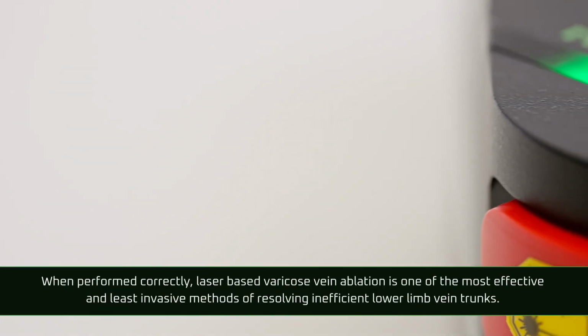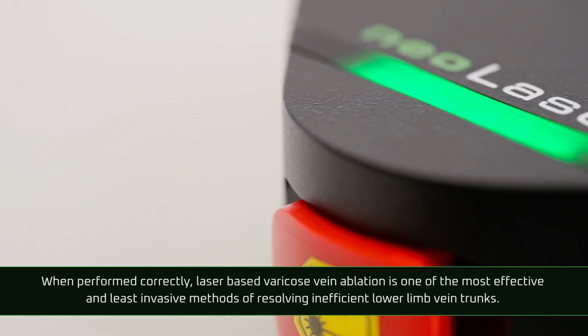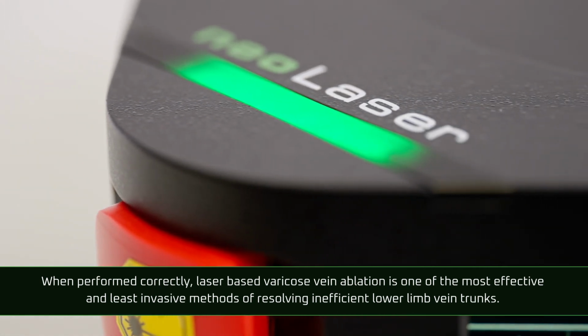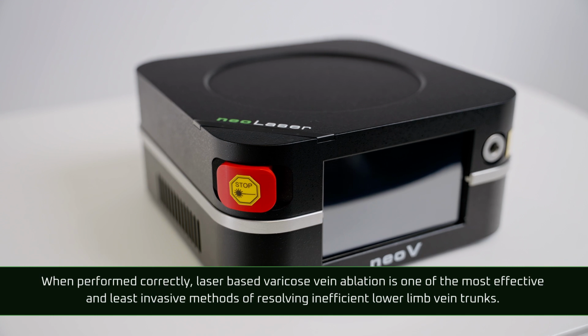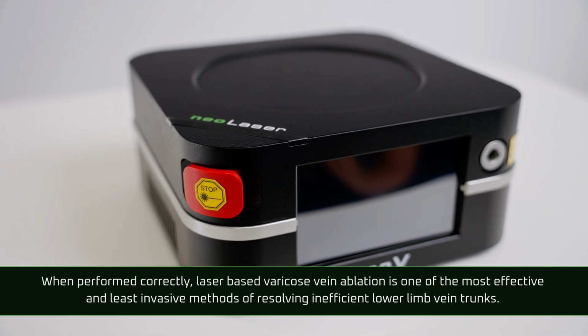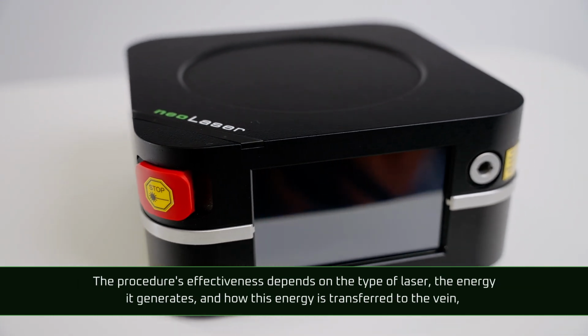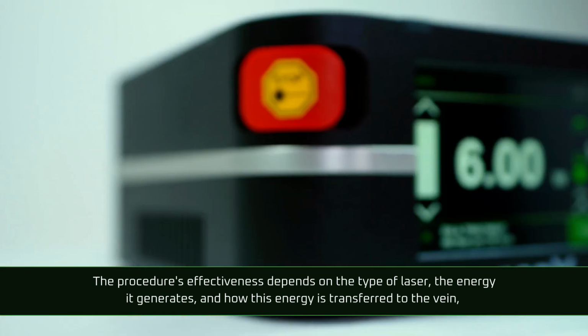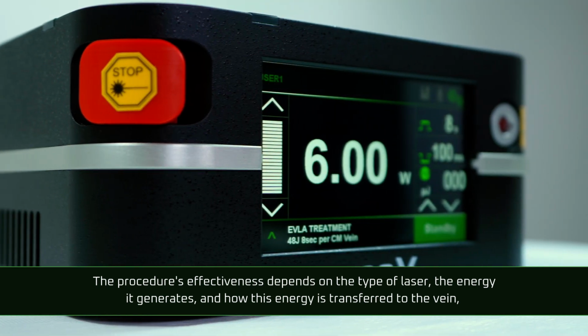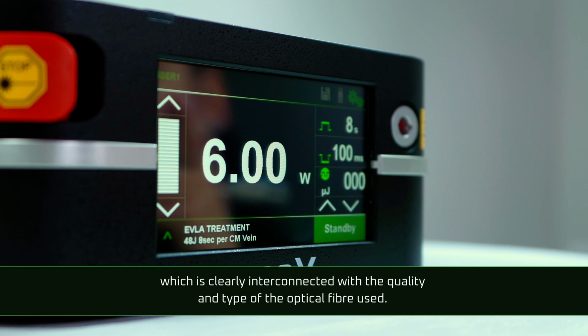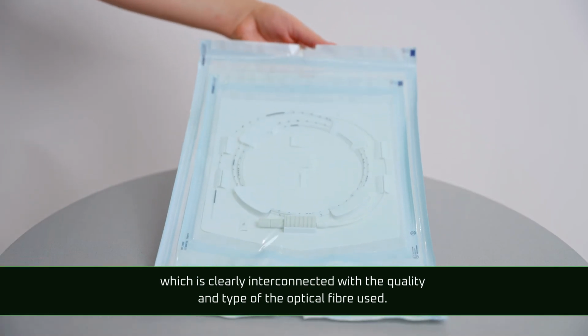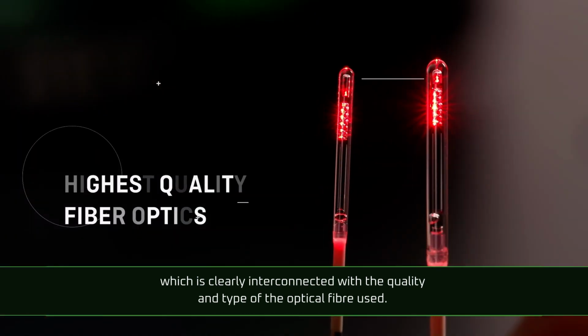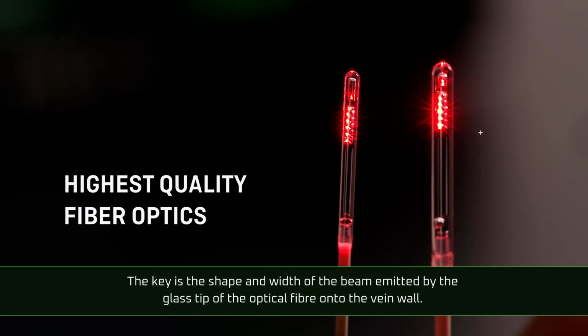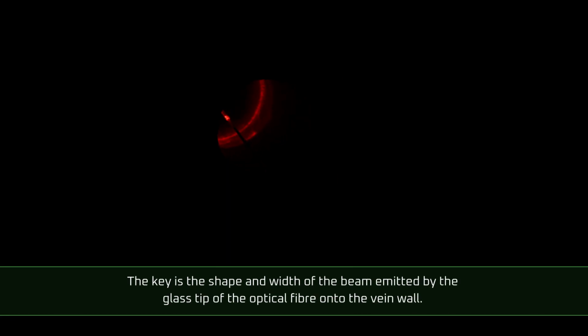When performed correctly, laser-based varicose vein ablation is one of the most effective and least invasive methods of resolving inefficient lower limb vein trunks. The procedure's effectiveness depends on the type of laser, the energy it generates, and how this energy is transferred to the vein, which is clearly interconnected with the quality and type of the optical fiber used.